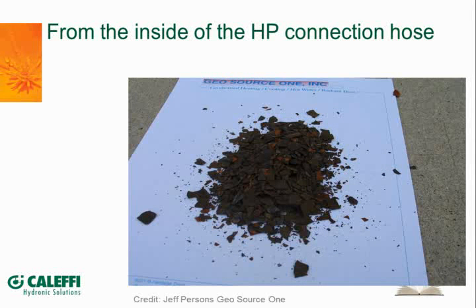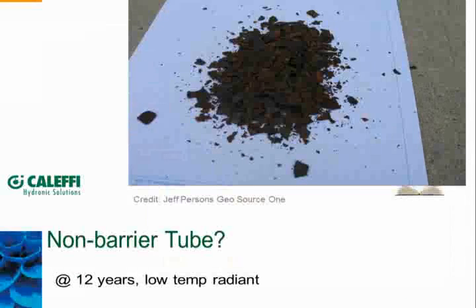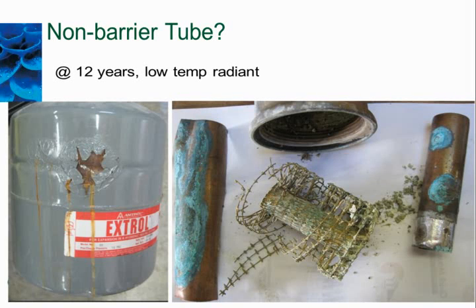Sounds like some of the old radiant hose we had out there that would sludge up from early tube that didn't have oxygen barriers on it. We ran them at high temperatures, and this is what came out of those systems. If you found a hard crust here, I'd almost bet these hoses, essentially like automotive radiator hose but rated for about 100 psi or better, may be contributing to that, and it might be an oxygen barrier issue.